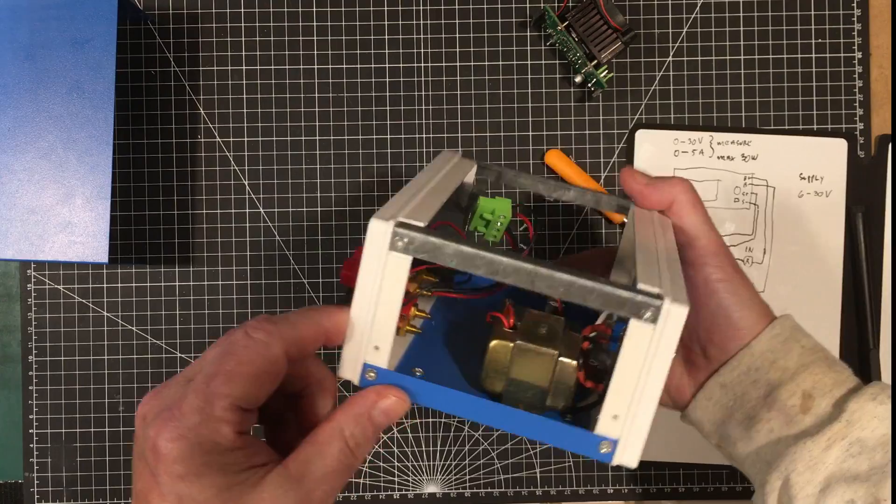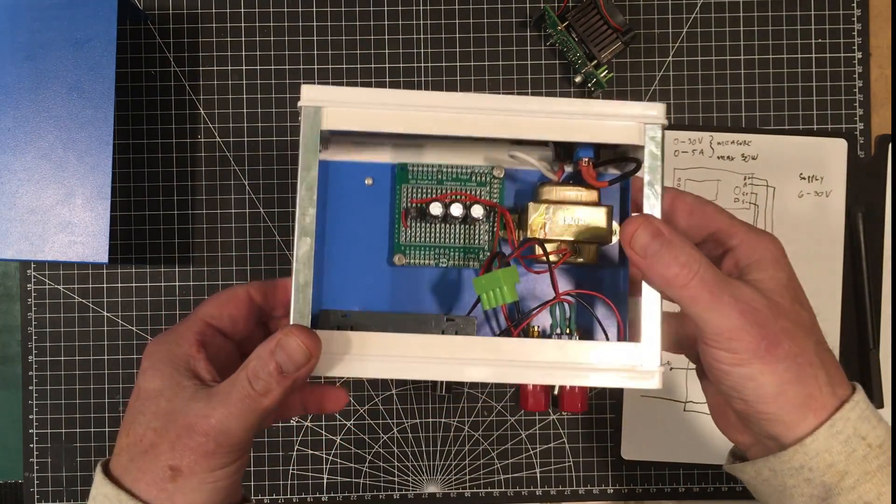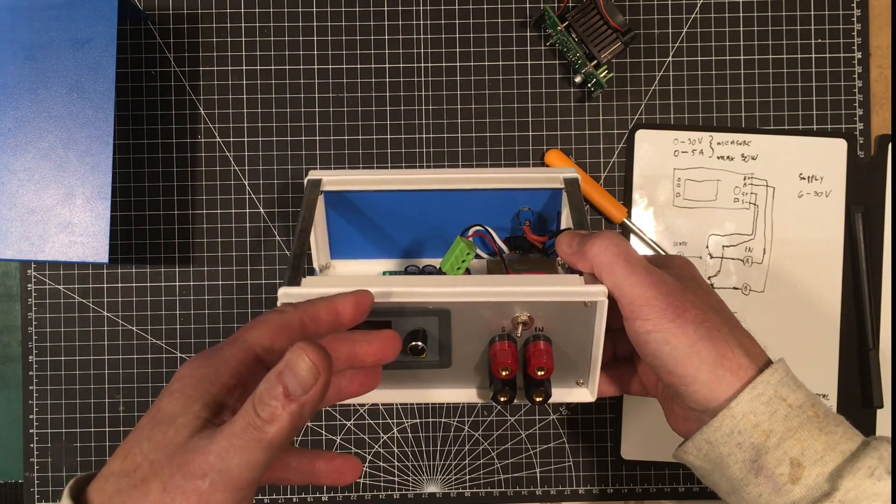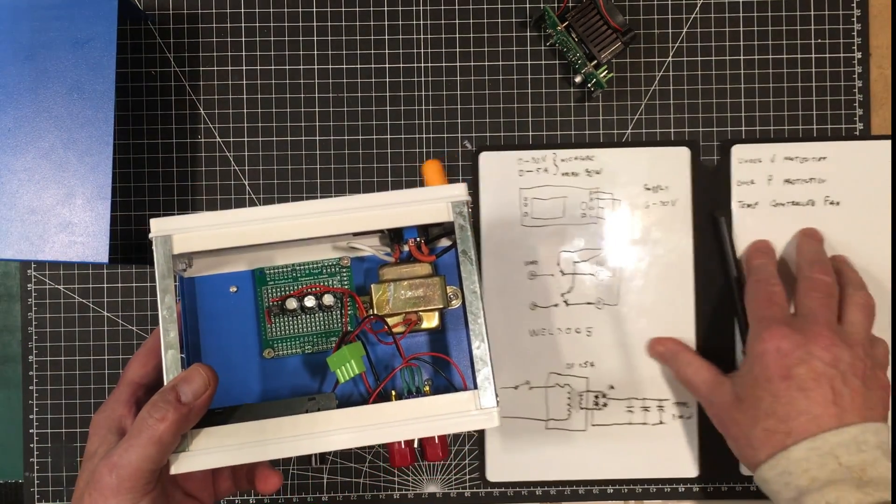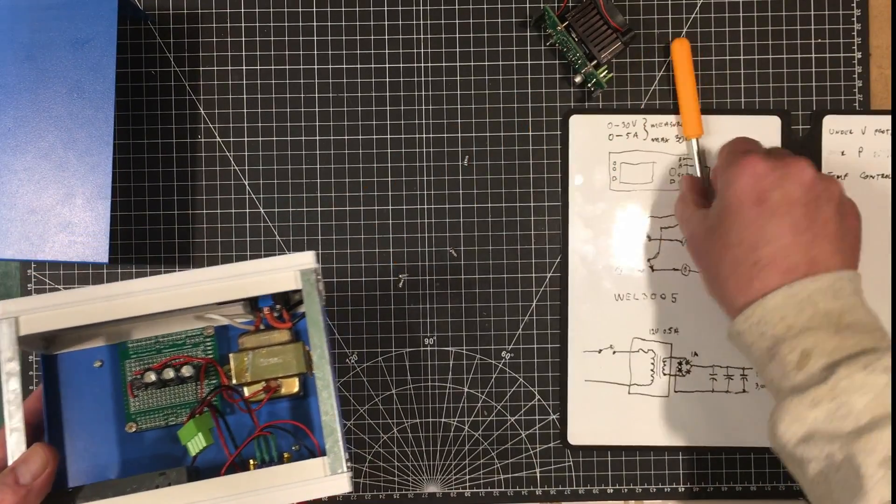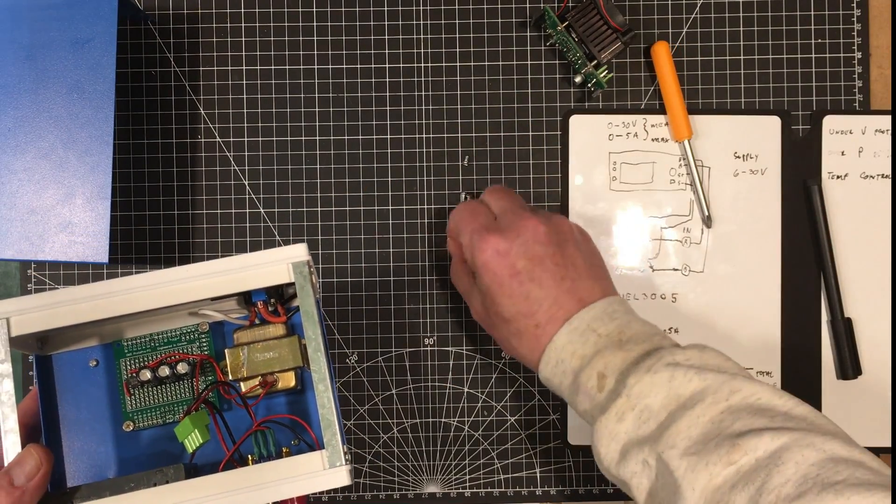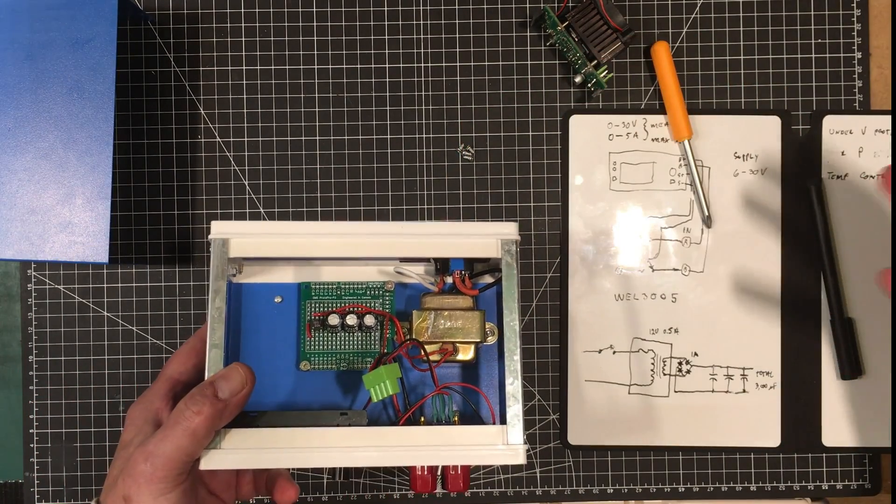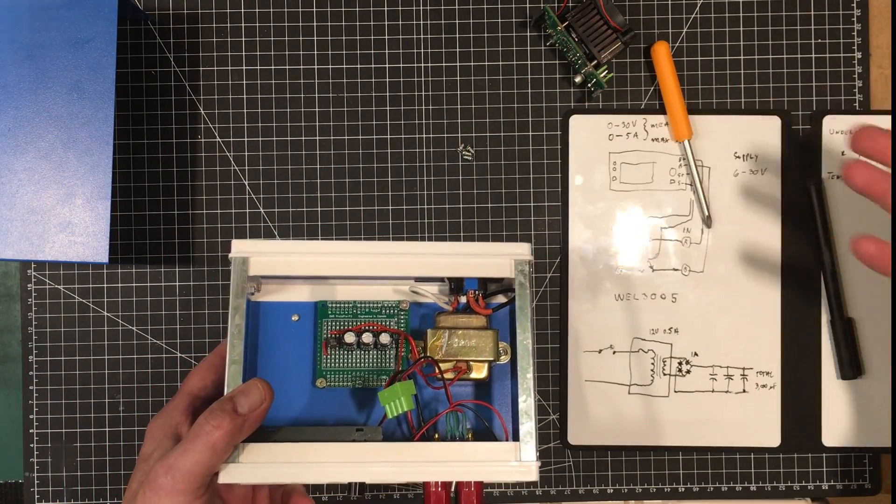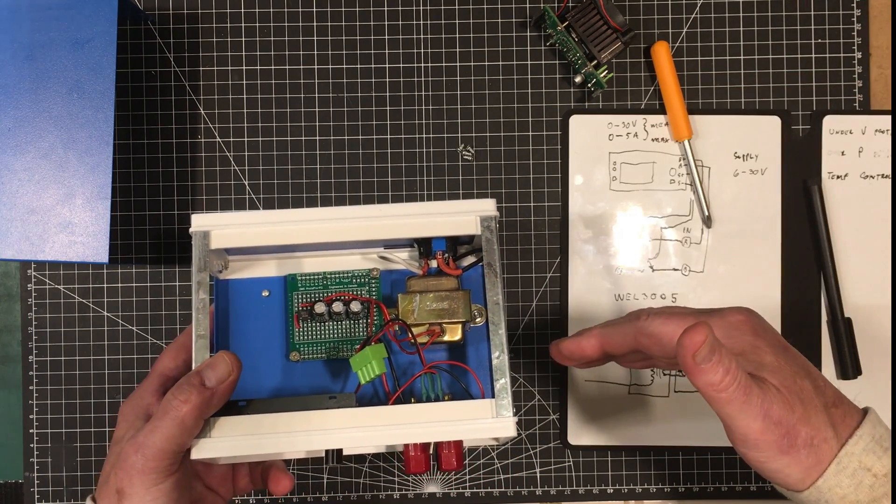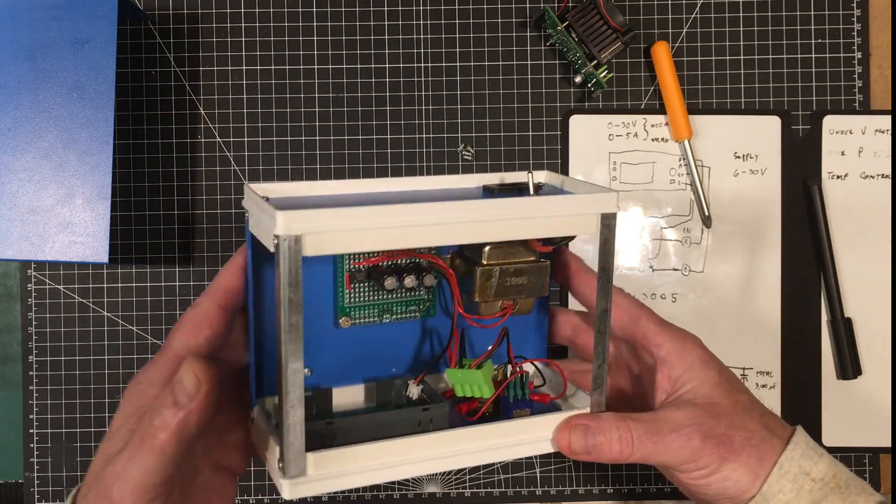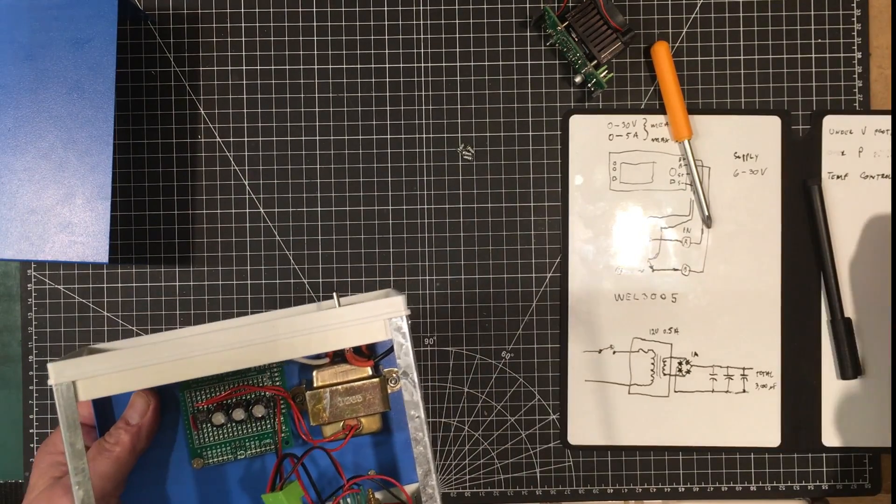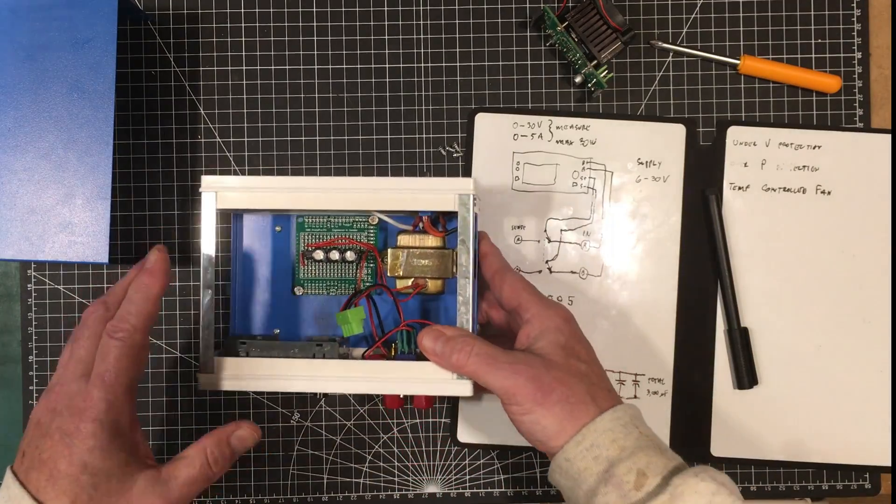That's it. It all together makes up this nice little DC load. It has specific features for looking at batteries such as the under voltage protection which is a very nice feature. No matter what battery you have, whether it be a lead acid battery, a lithium battery, a nickel cadmium or nickel metal hydride battery, you don't want to bring the voltage down to zero because basically that just means you've destroyed the battery. So in any of those cases it's good to have that under voltage protection which it does have.